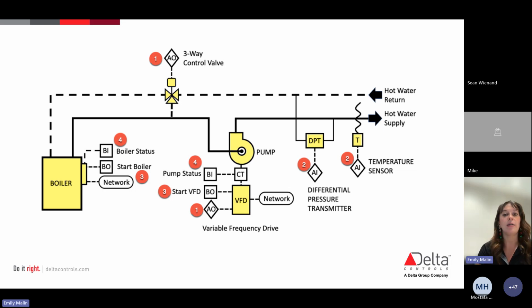Some of the inputs that you'll see on boiler systems in general are, like I said, the temperature, pressure, and flow sensors, as well as your thermostats and even your set points inside of those zones. And then you can also have things like your outdoor air temperature sensors. Your outdoor air temperature sensor is going to be used for weather-based adjustments. And again, we're starting to talk about these advanced control sequences, maybe being able to do some predictive control. If we know it's going to be a really cold day, maybe we, like Moose said, put in a time delay. That's where you're going to start to have your virtual inputs and outputs. Okay, we're measuring the outdoor temperature with our outdoor air sensor, and it's really, really cold. We know work starts at 8 a.m. Let's put in that time delay to start at 7:50 to heat up our space. So again, all of this is just building to a point where we can start to control all of these systems together in an efficient manner.